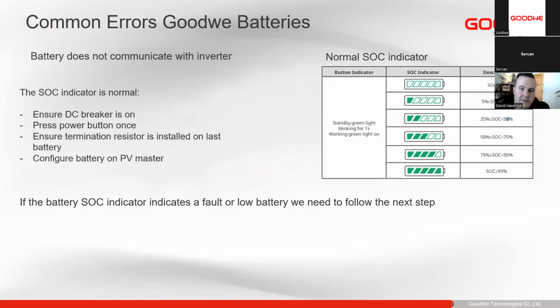So next, one of the common errors for the batteries is the battery might not communicate with the inverter. So we need to make sure that the SOC indicators are indicating normally on our batteries. If there's any alarm or any fault in the batteries, the SOC indicator will indicate the alarm that we're receiving. So we need to make sure that the DC breaker is on. We press the power button once on the batteries, and then we can view and observe the SOC indicator.